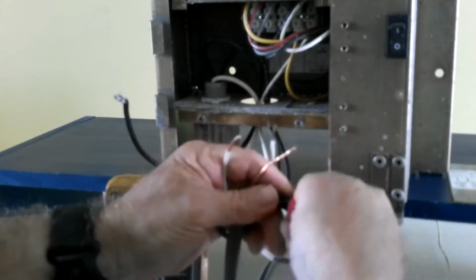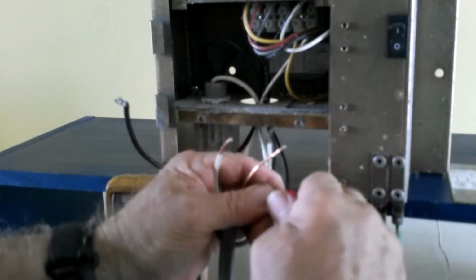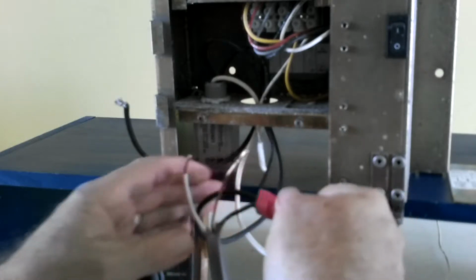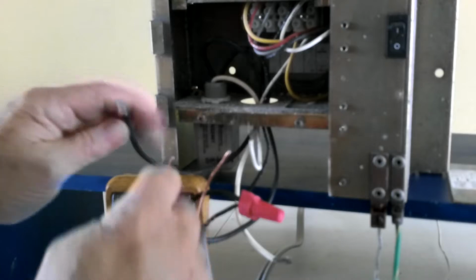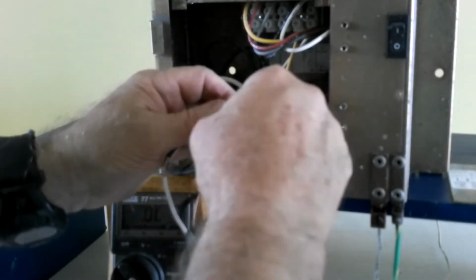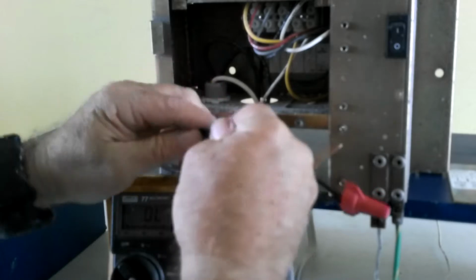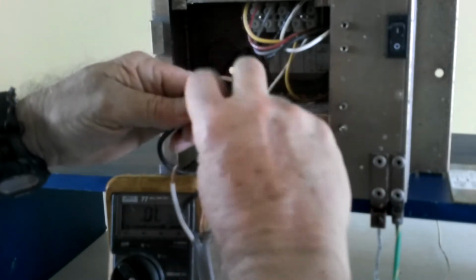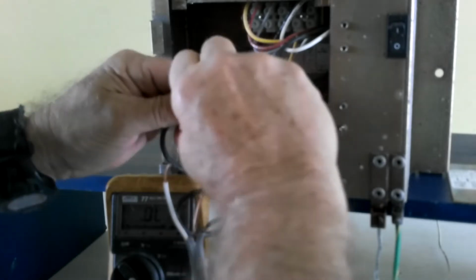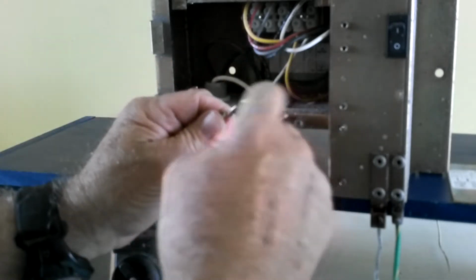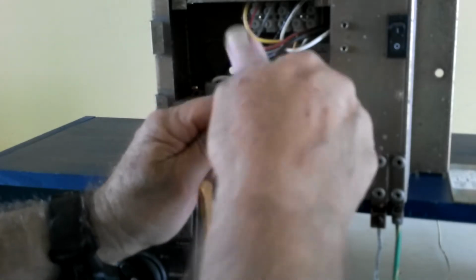Make sure your connections are tight and solid. Make sure you use wire nuts that are of proper size. Next, we want to take the other black lead from the surge arrestor, connect it with the neutral white lead from the transformer, and that connects to the neutral white lead coming from your power supply. Again, make sure your connections are tight and solid so that everything will work properly.